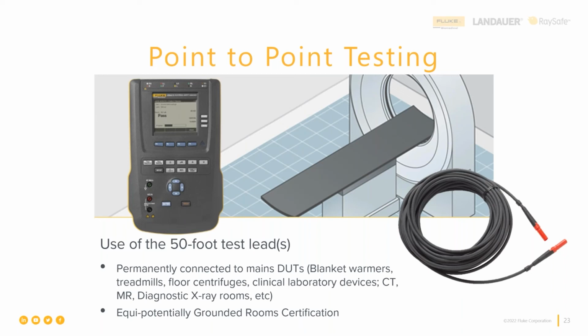And the room location matters. It's within 6 feet surrounding any patient treatment area. So in some operating rooms, the surgical table may be moving, not just changing position, but moving physically to a slightly different location. There's a new area that we need to test within 6 feet, and we need to make sure there are no ground loops that could cause unknown leakage current to be flowing, because the patient is very vulnerable in those locations.